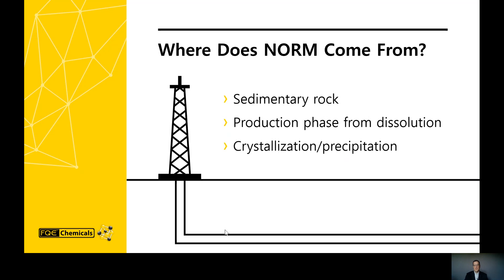Radioactive isotopes and salts have been in equilibrium in subterranean sedimentary rock for millennia. But during oil and gas extraction, these isotopes and salts are brought to the surface and appear mainly in the water that is co-produced with the oil and gas. These radioactive progeny, once in equilibrium, enrich the surface, and with pressure and temperature changes, they can reach saturation points and precipitate and crystallize out of solution, along with sulfate and carbonate deposits as mineral scale or sludge in pipe and other related equipment.